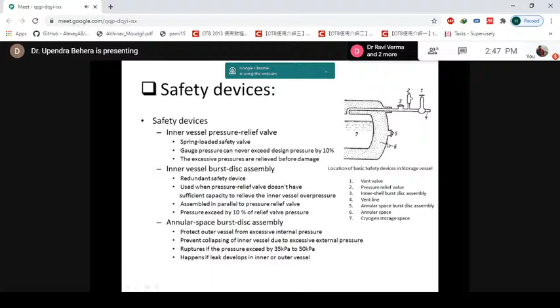Then an annular space burst disc assembly is also needed to protect the outer vessel from external pressure. If at all external pressure is coming to the inner vessel, then the pressure will increase here and this has to open. It also prevents collapsing of the inner vessel due to excessive external pressure. Okay, and if the pressure within this interspace exceeds 35 kilopascal to 50 kilopascal, this rupture disc opens up or bursts. So then both these containers are safe. This happens generally when there is a leak from the storage space to the insulation space. When it is entering, the pressure goes dramatically high instantly, and so the rupture disc is here so that it can prevent bursting or failing of both the containers.